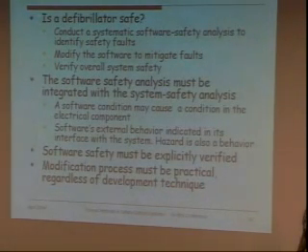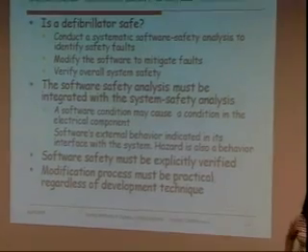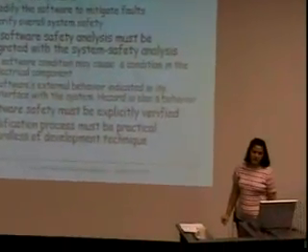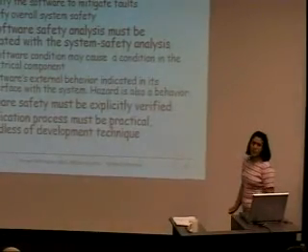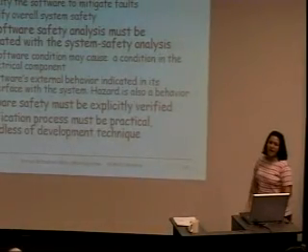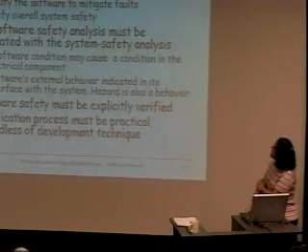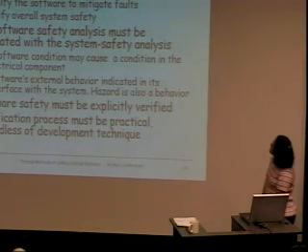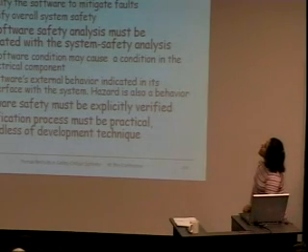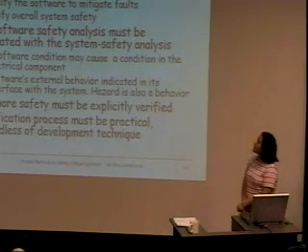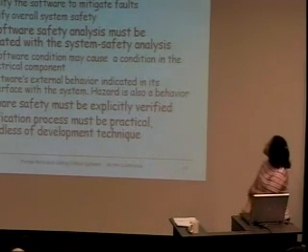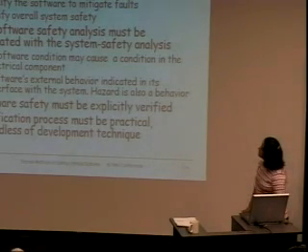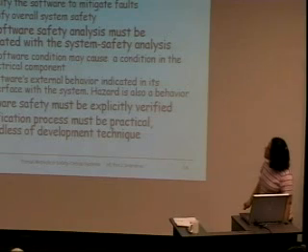At the University of Minnesota, several researchers decided to do a software safety analysis of the defibrillator to find out if the defibrillator is safe. They conducted a systematic software safety analysis to find the faults, then modify the software faults, and then finally verify the whole software safety.